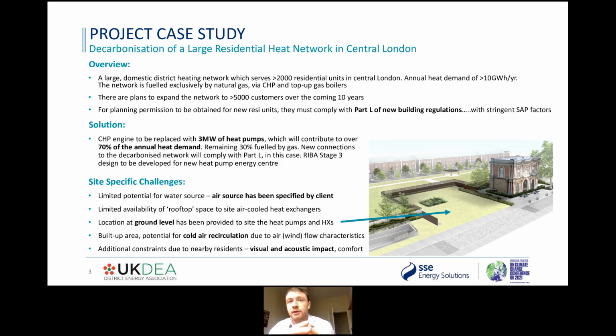As part of that, for planning permission for the new phases to be obtained, they must comply with Part L of the new building regulations, which essentially means they've got stringent SAP factors. In other words, they can't be served purely by natural gas. So the solution that we've developed, and this is something we'll be seeing a lot of in the coming years, will be removing a CHP engine and replacing it with 3 megawatts of air source heat pumps, giving over 70% of annual heat demand contribution at full build out, with the remaining 30% fueled by top up gas boilers.